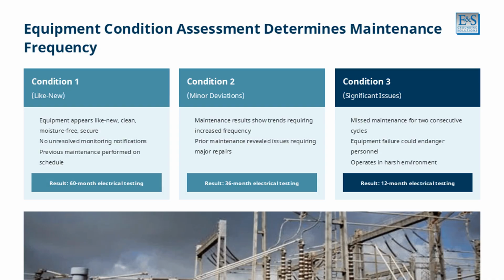Equipment condition assessment determines maintenance frequency through 3 classifications. Condition 1 represents like new equipment: clean, moisture-free, secure, with no unresolved monitoring notifications and previous maintenance performed on schedule. This results in the longest maintenance intervals, such as 60-month electrical testing.